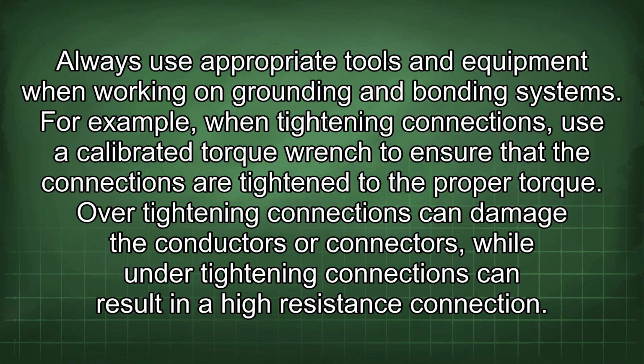Always use appropriate tools and equipment when working on grounding and bonding systems. For example, when tightening connections, use a calibrated torque wrench to ensure that the connections are tightened to the proper torque. Over-tightening connections can damage the conductors or connectors, while under-tightening connections can result in a high-resistance connection.